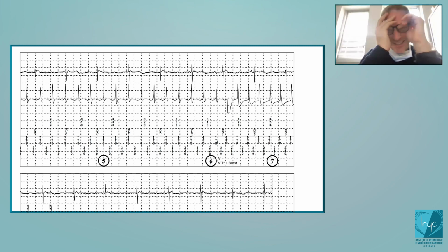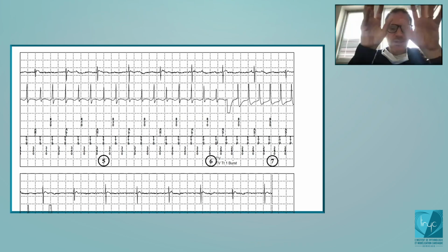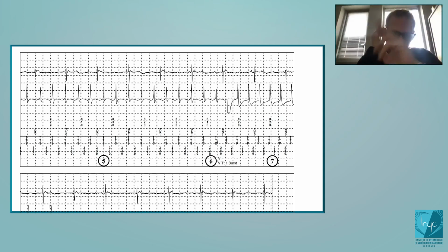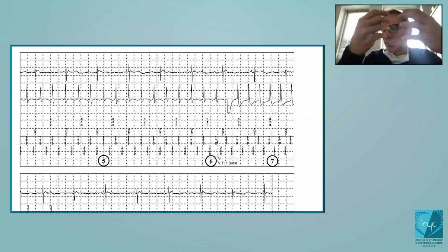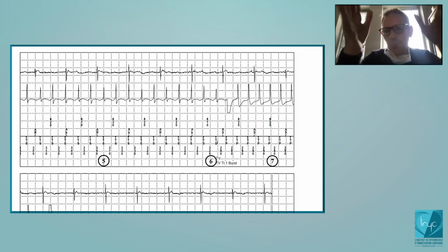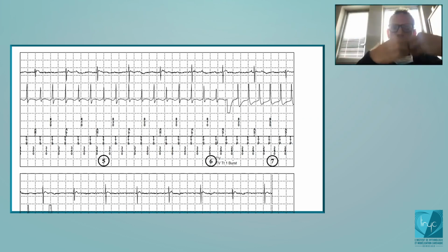Okay, so once more, in Medtronic devices, the huge specificity is that the way the counters work is completely different in the VT zone and the VF zone. That's a bit the same in Biotronik devices. For all the other competitors, the way you count in the VT zone and the VF zone is the same. It's probabilistic both in VT and in VF. In Medtronic, that's different, and that's a huge difference.